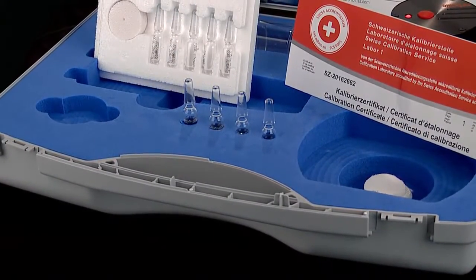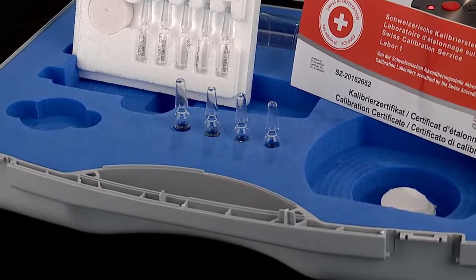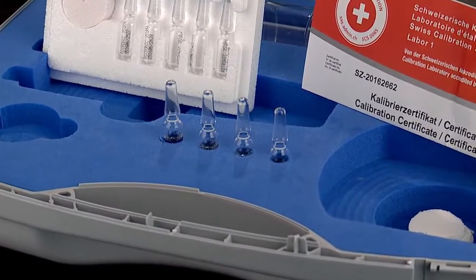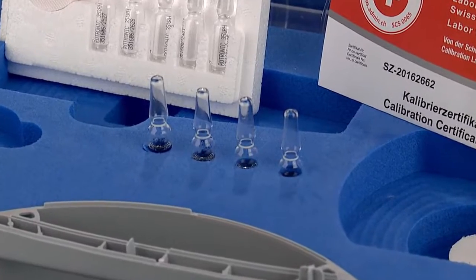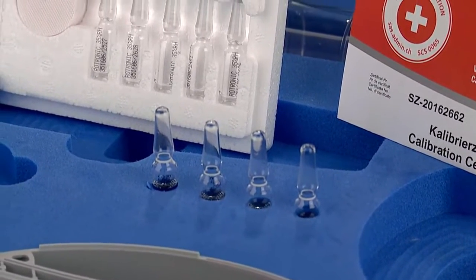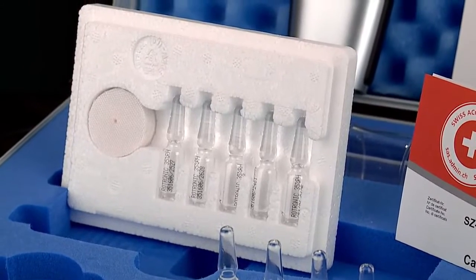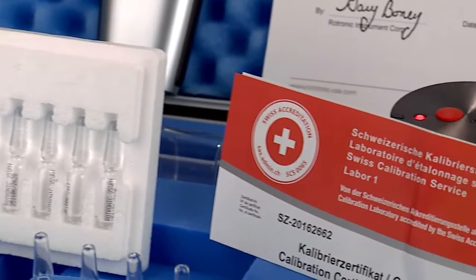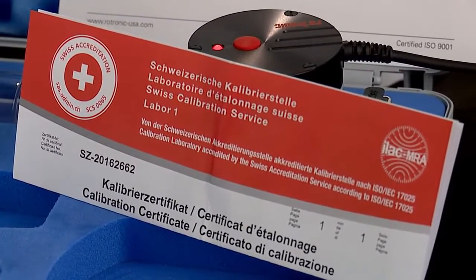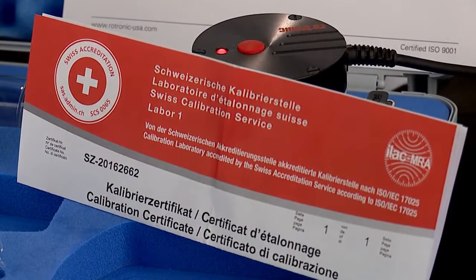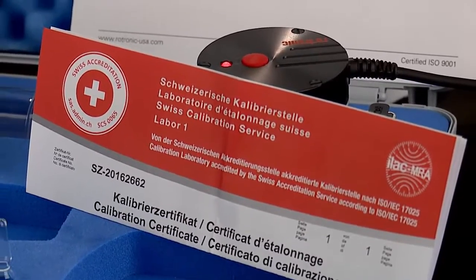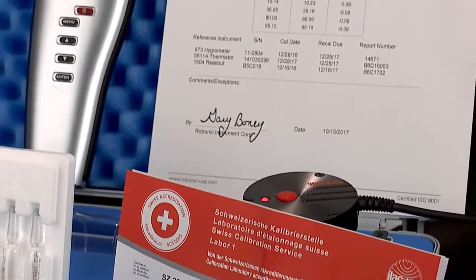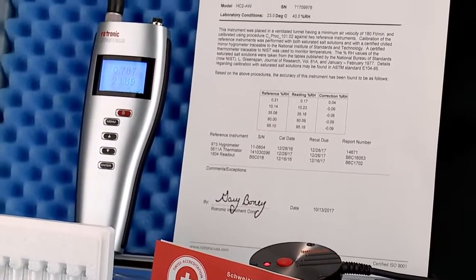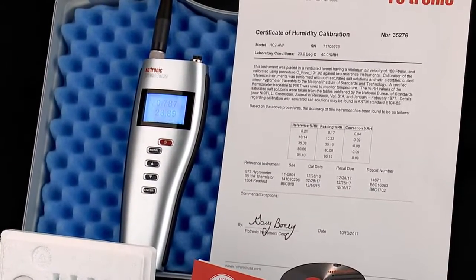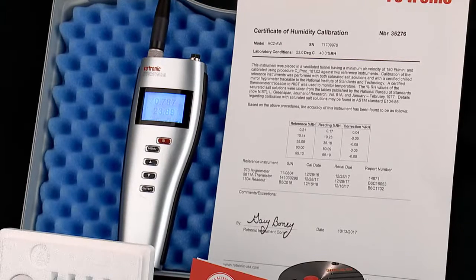All Rotronic AW systems come with calibration solutions which are presented in single-use glass vials. Each pack of 5 vials comes with a calibration certificate detailing the important variables of the calibration solutions. Standard calibration points for the Rotronic AW probe are 0, 10, 35, 80, and 95% RH. When purchased, each AW probe is freshly calibrated and a calibration certificate is included. However, if all of the desired AW tests are at similar points, it is acceptable practice to simply bracket the test point with 2 calibration points. This all depends on the SOPs of your organization.